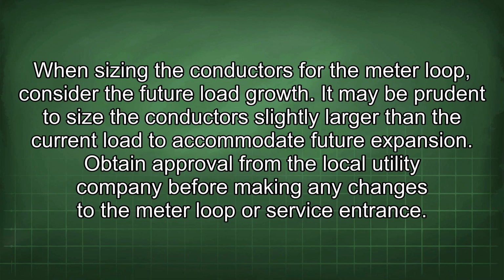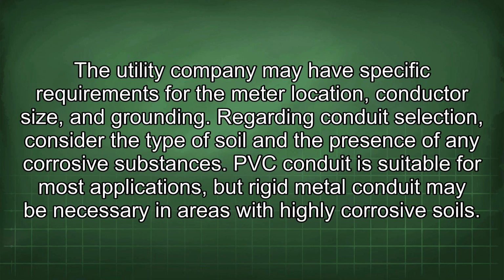When sizing the conductors for the meter loop, consider the future load growth. It may be prudent to size the conductors slightly larger than the current load to accommodate future expansion. Obtain approval from the local utility company before making any changes to the meter loop or service entrance. The utility company may have specific requirements for the meter location, conductor size, and grounding.